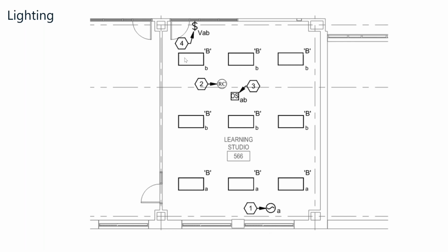We set the classrooms up to be controlled on vacancy, meaning lights don't come on automatically when you walk in. You have to hit the controller on the wall, keynote 4, to turn the lights on. If the occupancy sensor doesn't see movement, it shuts off. We didn't want someone who forgot their keys or phone to have all the lights come on for just a few seconds and then stay on for 15 minutes. So we wanted that conscious effort to turn lights on for class, then let automatic controls take over for the daylighting zone and the interior lighting.